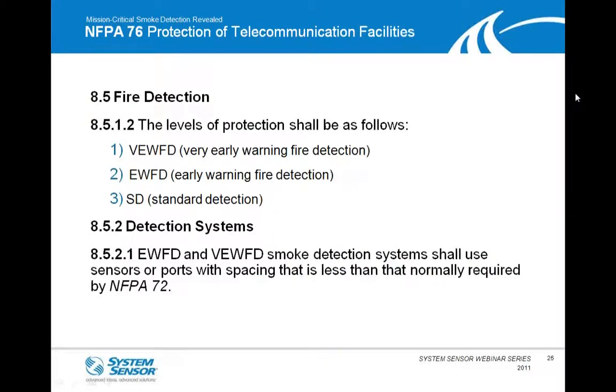Getting a little more detailed into NFPA 76, Section 8.5, which specifically starts talking about fire detection. Section 1.2 defines the levels of protection, and this is where many people think of when we're talking about NFPA 76. It describes the highest level of very early warning fire protection. The next stage down is early warning fire detection, or EWFD, and then also standard detection. Again, with very early warning fire detection, a lot of people jump to the conclusion that aspiration is the only thing that can meet that. Quite honestly, some other laser-based spot detectors and other products can meet that. But again, most commonly, aspiration is used to meet that need.